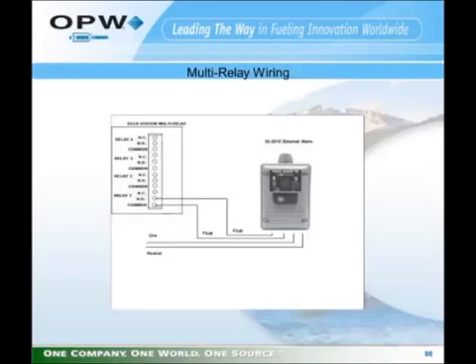Should you want to control an external device, let's say that you want to turn off a device when the relay energizes, then your connection would be common to normally closed. So when it's at relaxed or unenergized state, that would be your circuit from common to normally closed, and on alarm, common to normally open would then open that circuit and disable that external device.